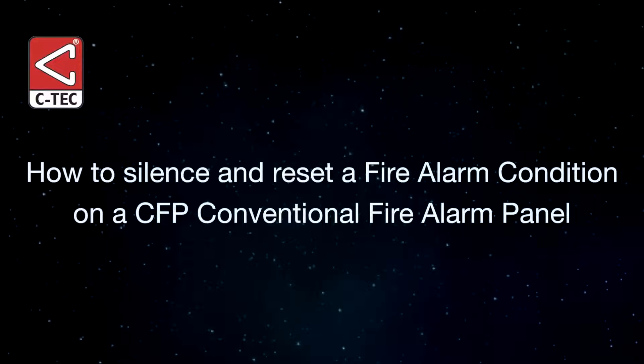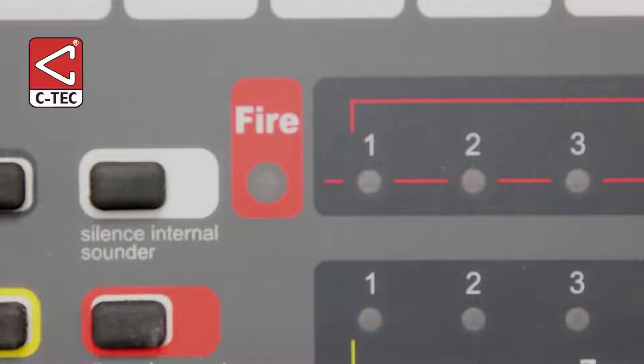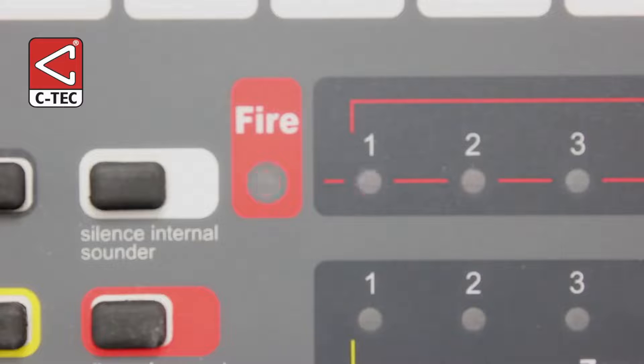How to silence and reset a fire alarm condition on one of C-TEC's CFP conventional fire panels. In a fire alarm condition, the panel's internal beeper will sound to inform you that an alarm has been detected. The panel's red general fire and at least one of its zonal indicators will flash to show you which zones are in a fire. In this case, zone 1 is in fire.